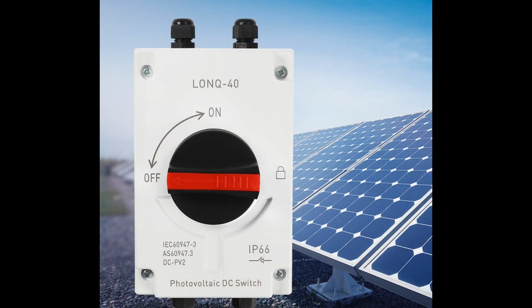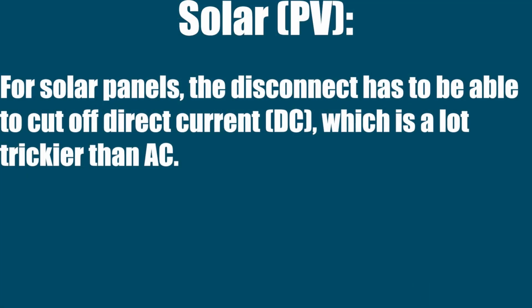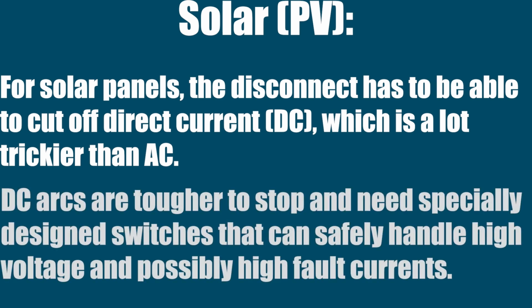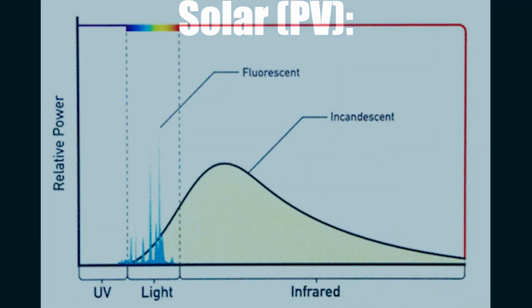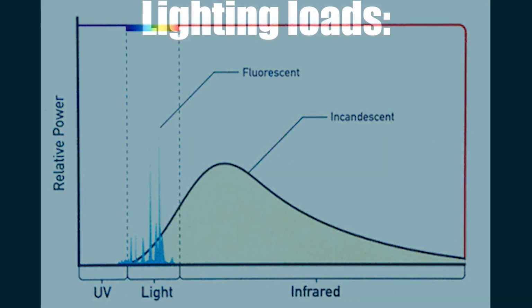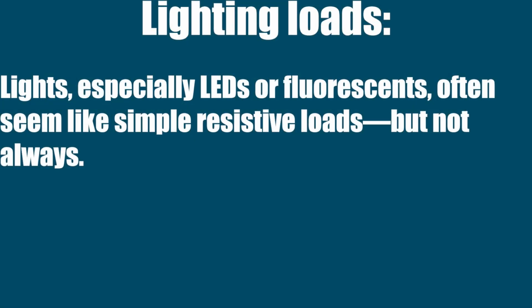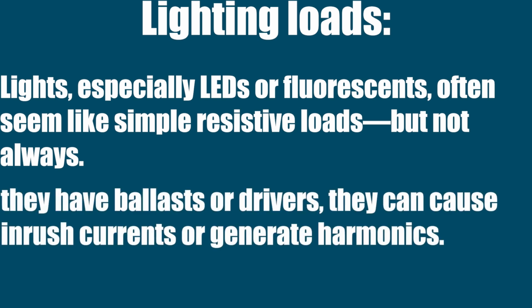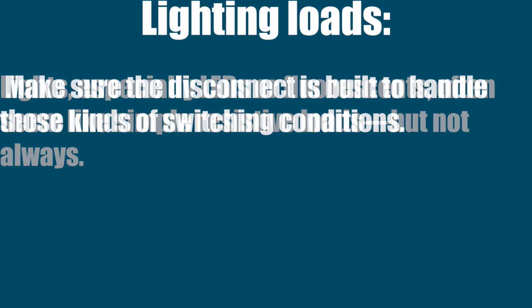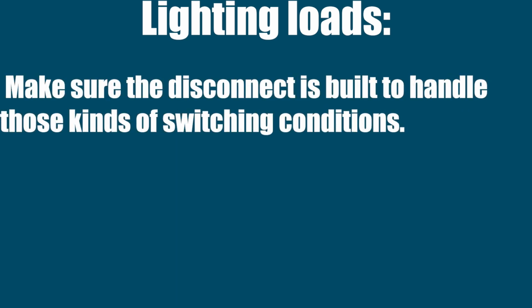Solar or photovoltaic setups, they need special DC rated switches. For solar panels, the disconnect has to be able to cut off direct current, which is a lot trickier than AC. DC arcs are tougher to stop and need specially designed switches that can safely handle high voltage and possibly high fault currents. Lighting loads might look simple but still have quirks. Lights, especially LEDs or fluorescents, often seem like simple resistive loads, but not always, because if they have ballasts or drivers, they can cause inrush currents or generate harmonics. Make sure the disconnect is built to handle all of these kinds of switching conditions.